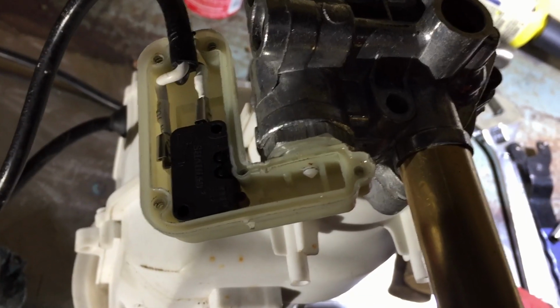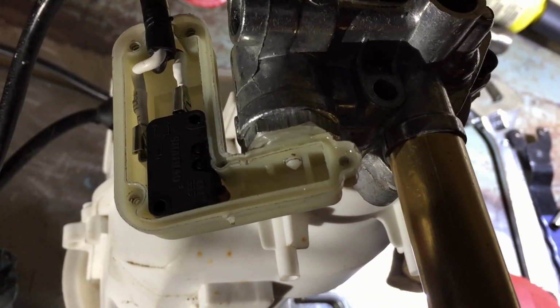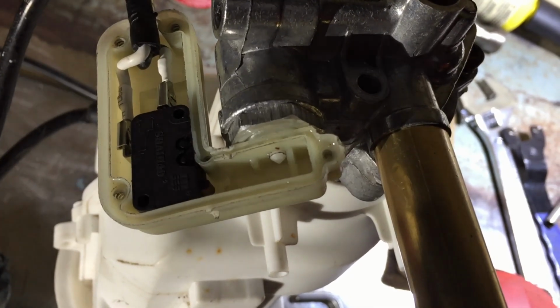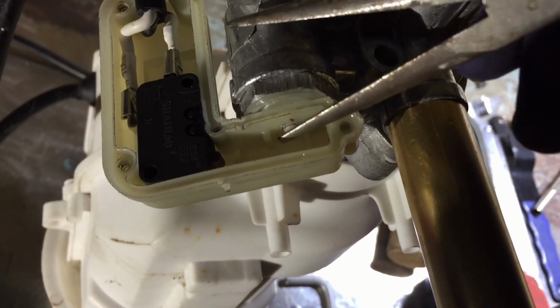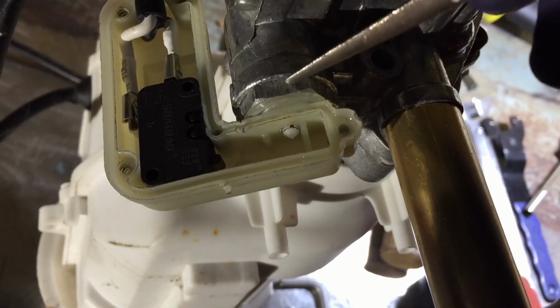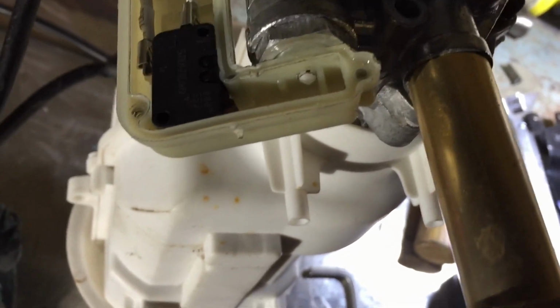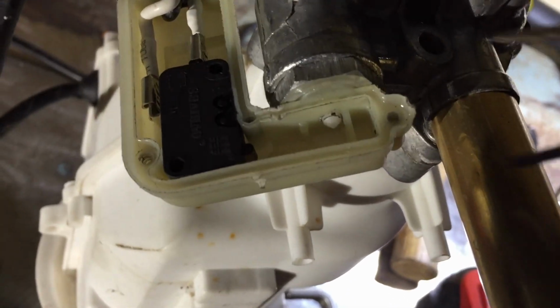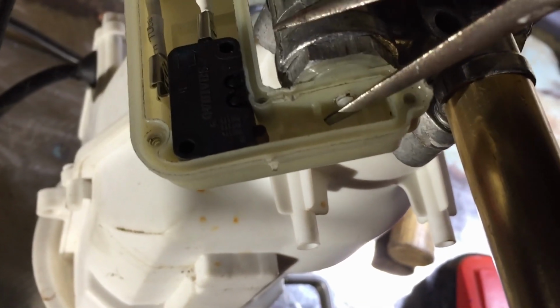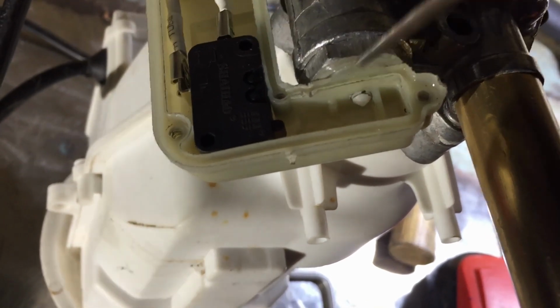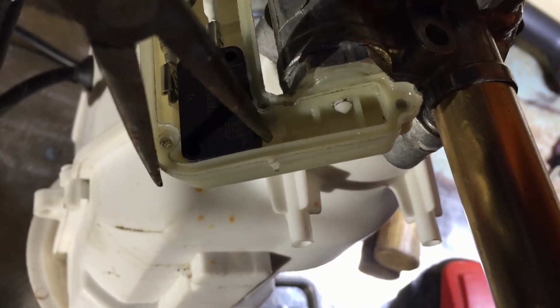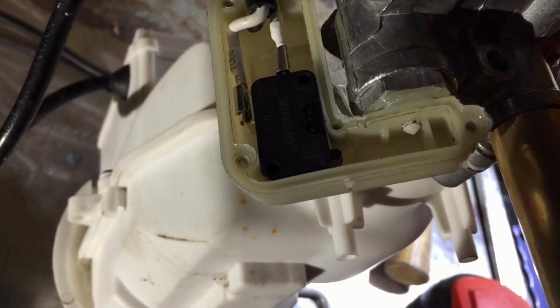So the other issue these units have is the motor not shutting off when it reaches pressure. That's because this little needle right here gets stuck inside this shaft. What happens is this needle comes out, pushes a little plastic piece up, and contacts this button, closing it. That just tells the motor to shut off.